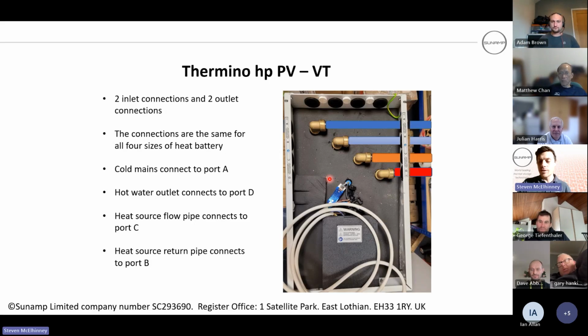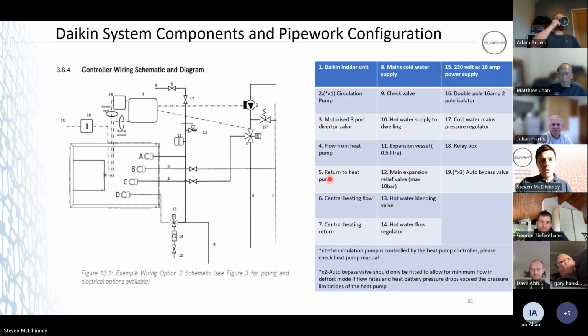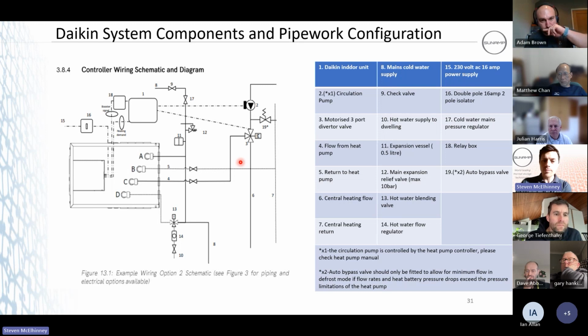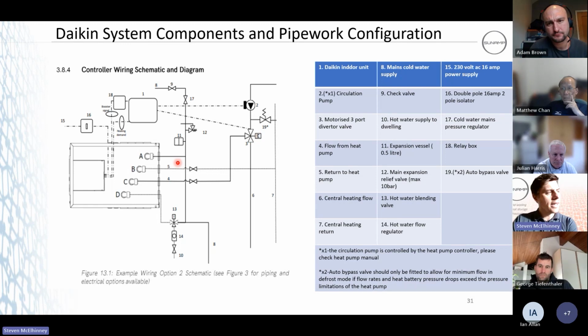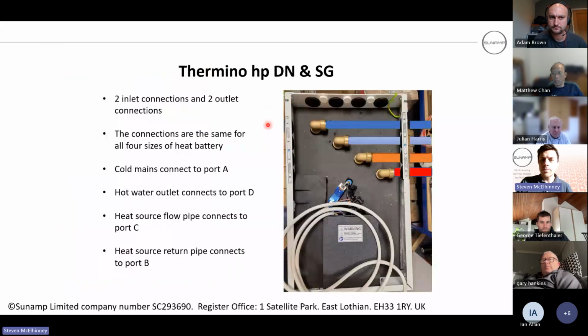So yeah, that's again, I feel like I'm just a broken record here. Just keep checking your manual if you come across different units you're used to working with. So yeah, Daikin systems, the most important thing for the heat pumps I've noticed since working with them is the flow rates. The heat batteries do have that pressure drop. So again, your 150s still have that flow rate situation. But if you're getting any flow issues, you will have to have your auto bypass fitted there to take up the slack, because the heat battery can only take in so much at one time. So that's why we say we only go up to, is that 12 kilowatt? 12 kilowatt heat pump.